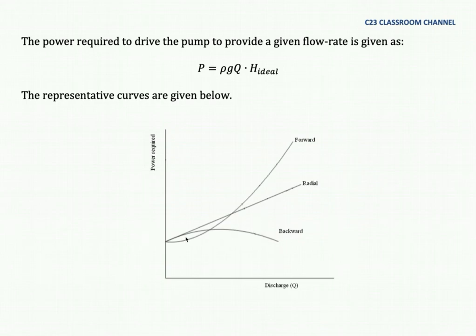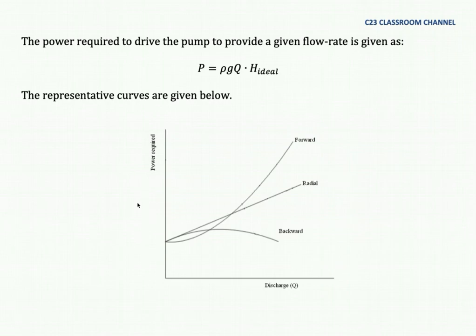For backward, it might not be too much different, but for radial and forward you will need more power to have more discharge. But if you see the relationship between discharge and head, you will find that if you increase discharge, sometimes the manometric head or pump head will not increase. It means there's no need to increase the discharge because it just only increases the power required.